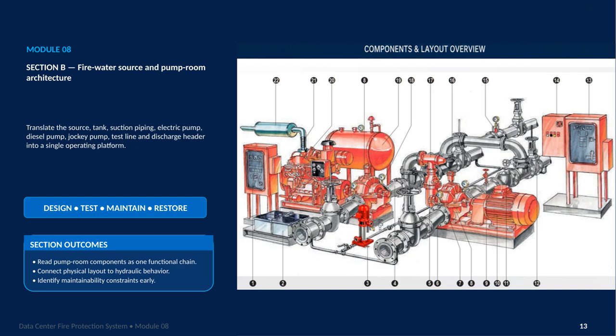That means we will examine how the physical arrangement of the pump room affects hydraulic behavior, including how water moves through the system and how the equipment works together under different operating conditions. We will also pay attention to maintainability from the beginning, because access, testing, servicing, and restoration are not secondary concerns. They are part of the design. By the end of this section, I should be able to read the pump room components as a functional chain, connect layout decisions to system performance, and identify constraints before they become operational problems. The working cycle is simple: design the system, test it, maintain it, and restore it when needed.